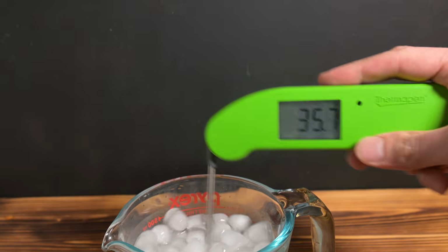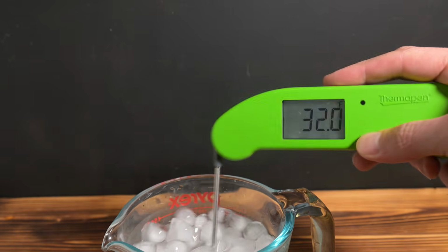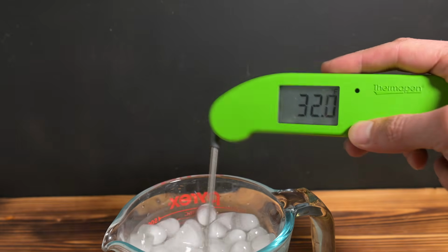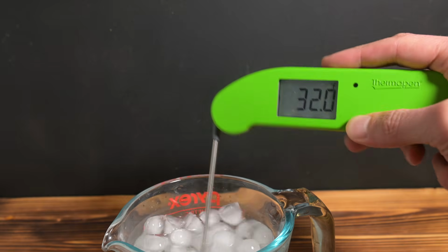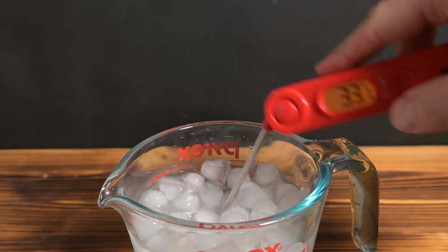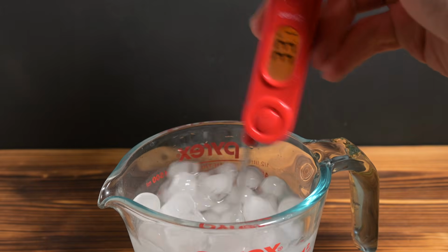To avoid inaccurate readings, make sure that you move that probe around in the ice bath, and that'll help keep it from resting on the side, the bottom, or directly on the ice. That'll absolutely impact the reading that you get. If you do this test correctly and your thermometer is accurate, it should read 32 degrees Fahrenheit inside of that ice bath. But all thermometers come with a plus or minus tolerance range, so you want to make sure that it's within that range. So if your thermometer says it's accurate to plus or minus 1 degree Fahrenheit, it should read between 31 and 33 degrees Fahrenheit. And if it's in that range, it's as accurate as it can be. You don't have to mess with it, just go ahead and leave it.